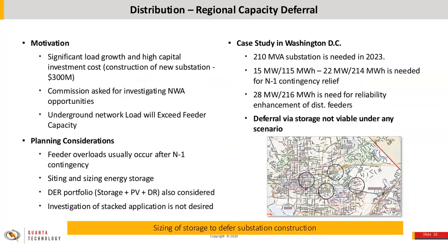In Washington, D.C., PEPCO, Potomac Electric Power, forecast a lot of load growth in the corner of the city behind Union Station, if you know the district at all. That's an area that today is changing from old warehouses mostly to upscale office buildings and some residential. A lot of construction going on. The existing underground network wasn't sufficient to handle the growth, and they're spending close to $1 billion to add 230 kV subtransmission. Yes, in Washington, D.C., 230 kV is subtransmission, and a new substation to serve that area.